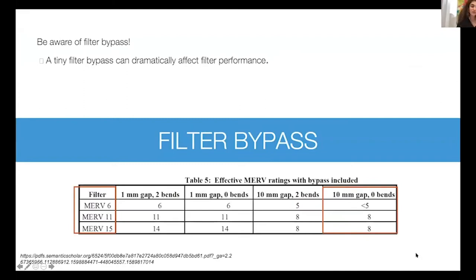The other one, which is extremely important, and I don't think we talk about it a lot, is filter bypass. By filter bypass, I mean when you put your filter in the air handling unit, if you don't fit it very well, you will have air gaps from the top, bottom, right, or left, or between the filters. Filter bypass is extremely important to take care of. To give you an example, there is a scientific study that looks at the impact of filter bypass on efficiency.